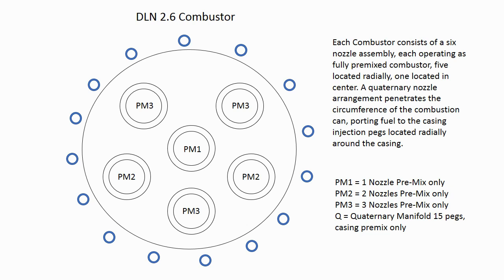PM1 consists of one nozzle which is premix only. PM2 consists of two nozzles which are premix only. PM3 consists of three nozzles which are premix only. The quaternary manifold contains 15 pegs, which are casing premix only.